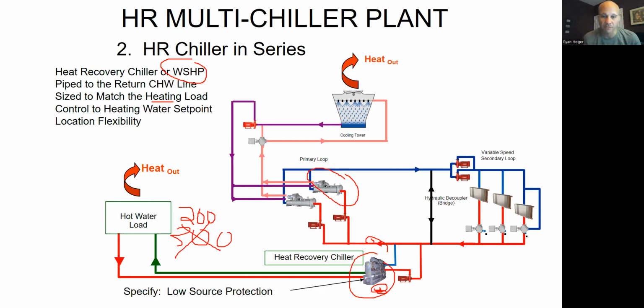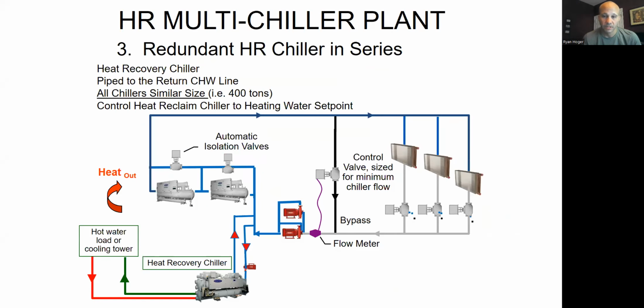The same thing could happen if you had this chiller plant set up that way. The cooling tower has to kick on to trim the difference, and when these two guys don't match, the regular boiler or hot water heaters have to kick on to trim the difference when these two guys don't match. All right, hopefully that answers that.